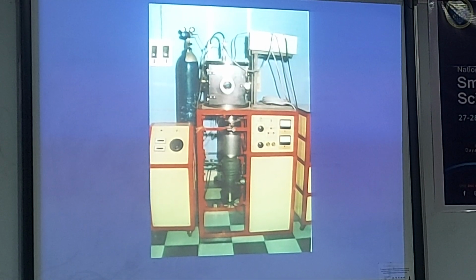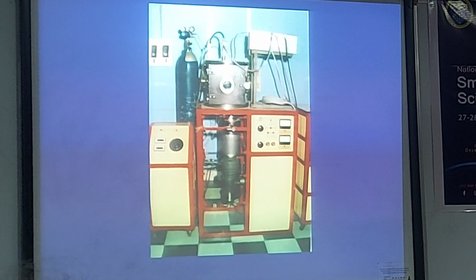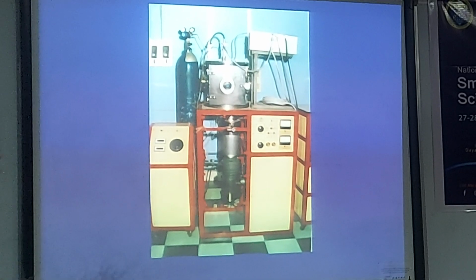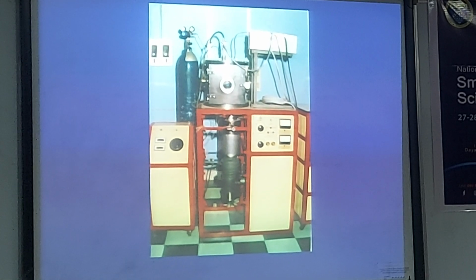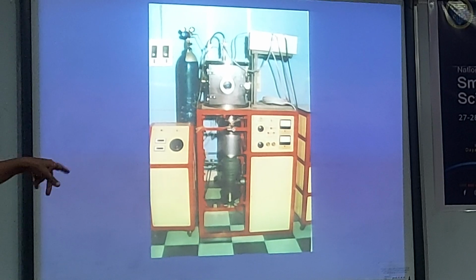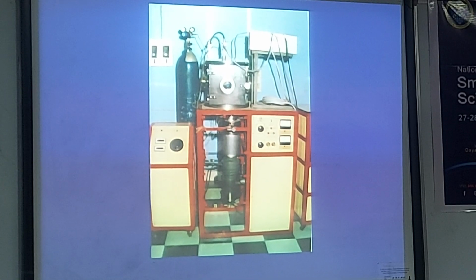This is a metal chamber, a box type metal chamber. This was also made in our laboratory by our student. On the lower side, what is shown is a diffusion pump backed by a rotary pump. This is an RF power supply. This is a gas cylinder. Normally, the inert gas argon is used. Sometimes, in order to do reactive sputtering, in addition to argon, we also use a reactive gas like oxygen. Then it's called reactive sputtering. There are various versions of that.